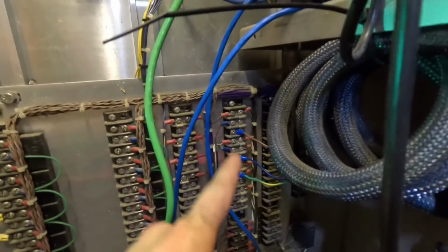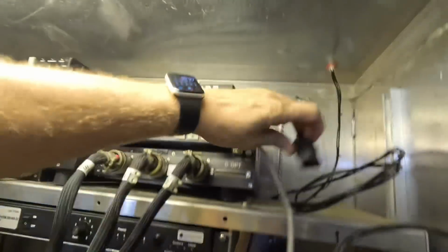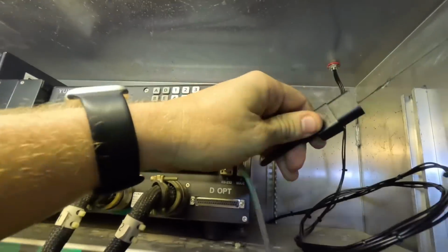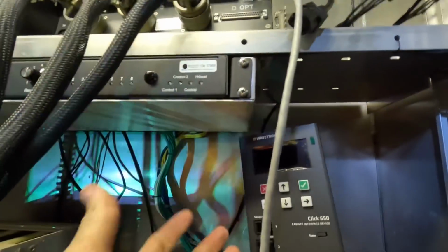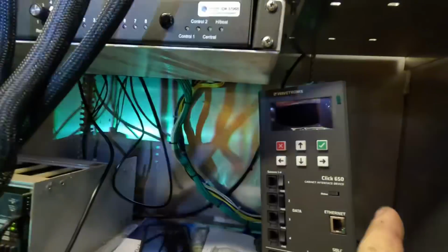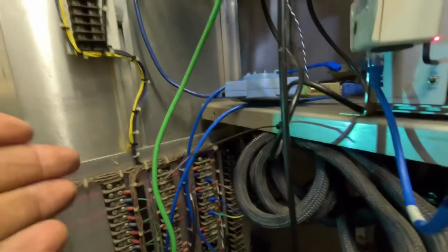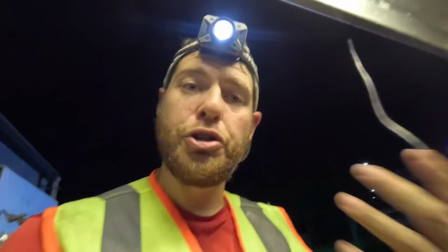Also, when you're wiring this stuff up, if you can help it, try to never have a load on this, meaning don't have this plugged into this device where it's drawing power while you're trying to hook up your power. You'll end up having arcs, and you could damage equipment by doing so. So, try to have it unhooked, do the ground, neutral, and then your hot, and you should be safe after that.